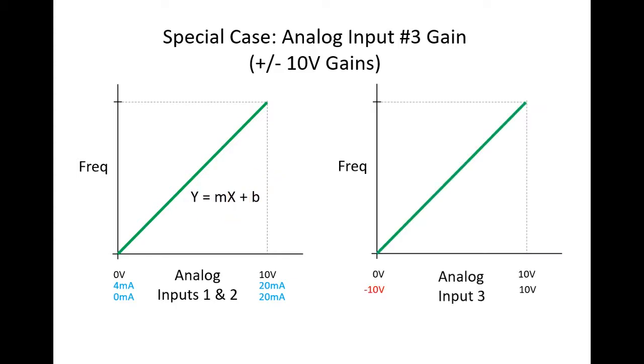The difference is analog input 3 has a gain parameter for the positive side and another parameter for the negative side. That's handy for when you have a process that normally runs in one direction, but you want to limit the max possible speed in the other direction using the negative voltage as an input. A good example of this is a reverse jog where you use the negative voltage for the reverse direction.